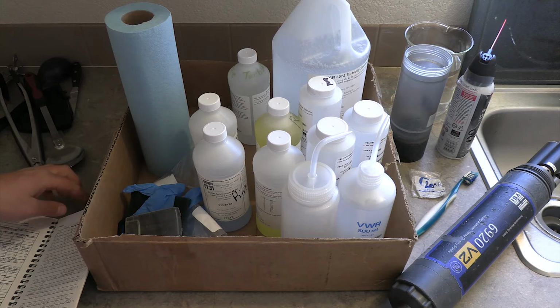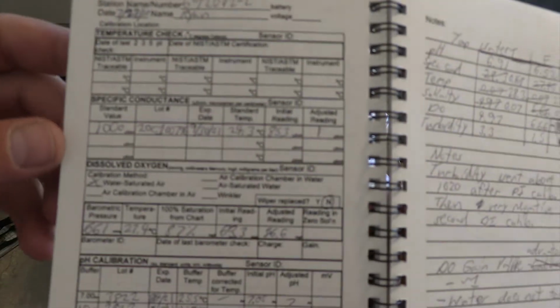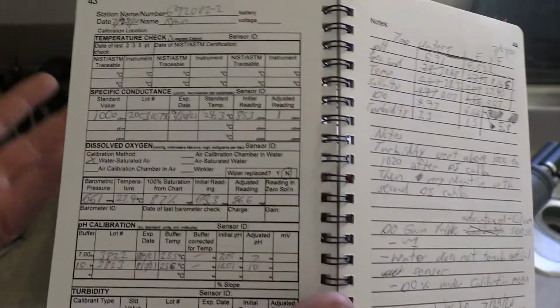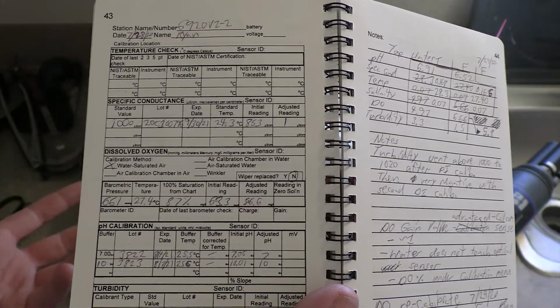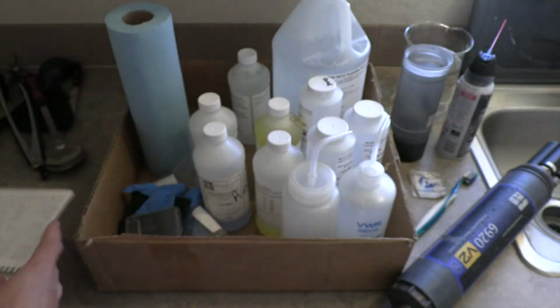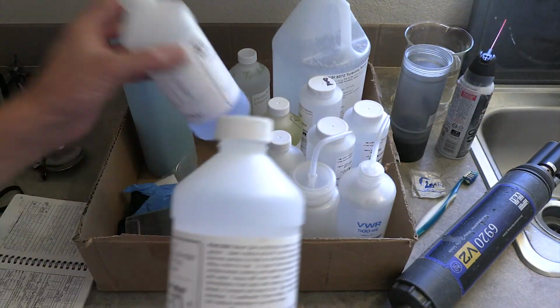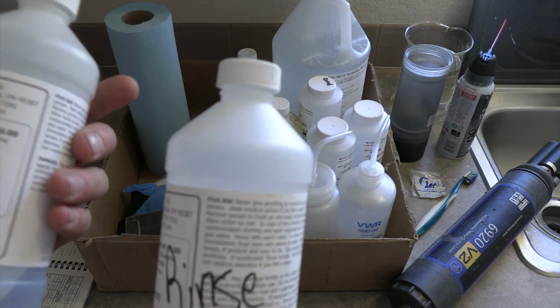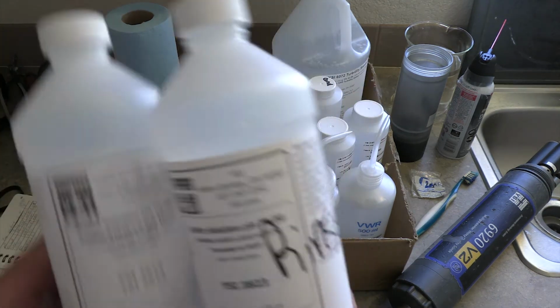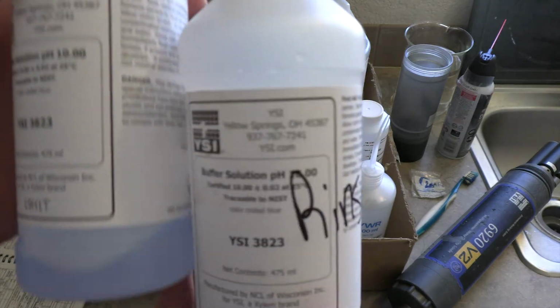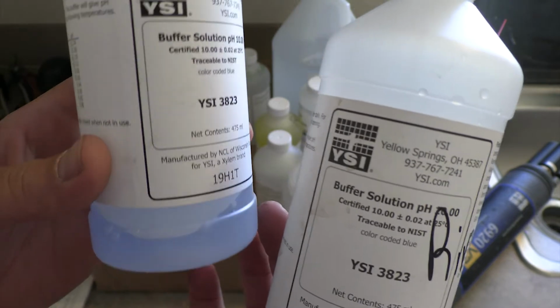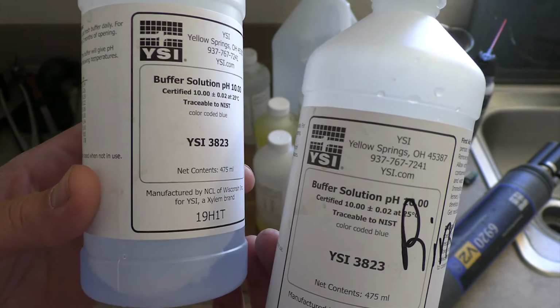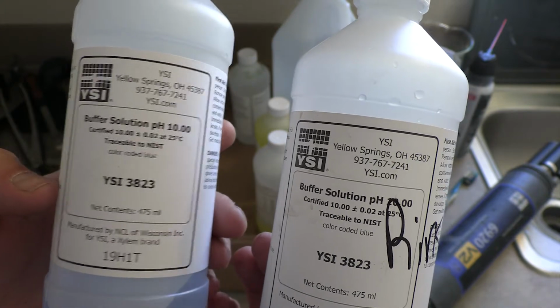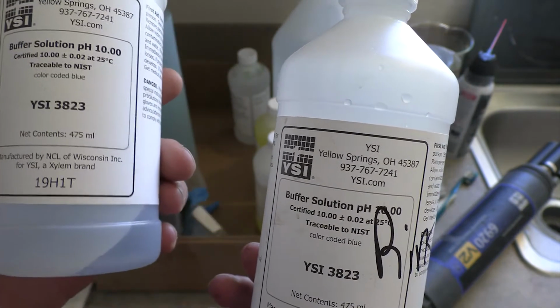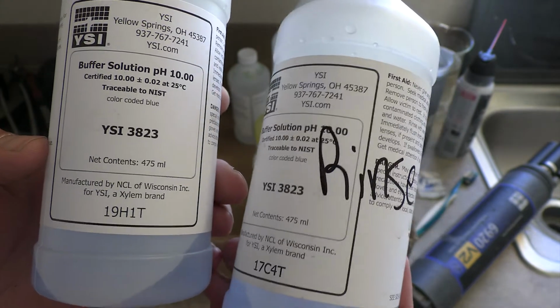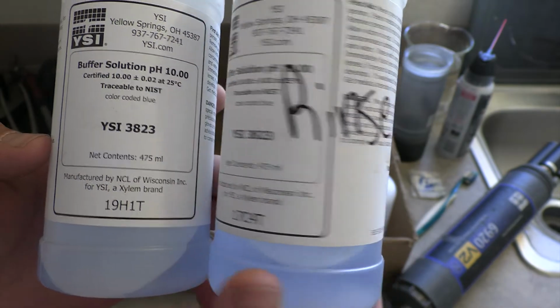All right, so next let's go back over to the book here, and the next one down is dissolved oxygen. So dissolved oxygen is great. You just put tap water in the bottom, about 2 inches. So we'll go over that in a sec. Then let's go to pH. So we have 2 pH. Pretty sure the blue is the 7. Nope, the blue is 10 and the yellow is 7. Same thing here. We have a blue, which is our 10 pH solution, YSI 3823, and there is a lot number at the bottom, 19H1T. And then we have our rinse. So just make sure you rinse once or twice before.